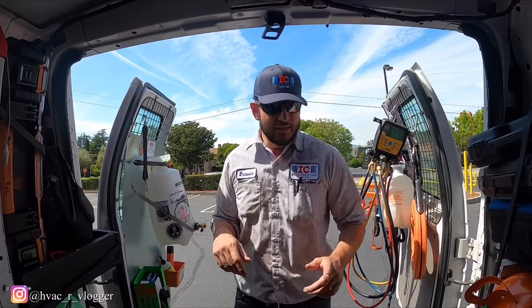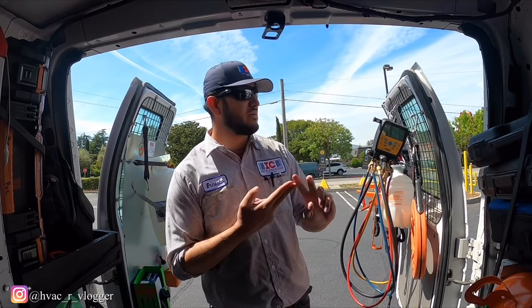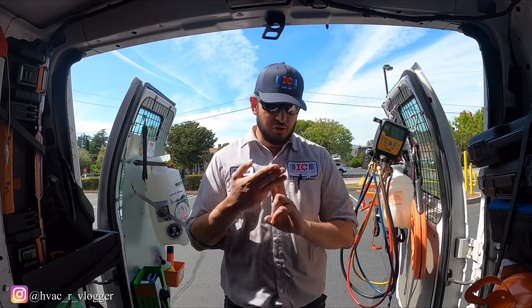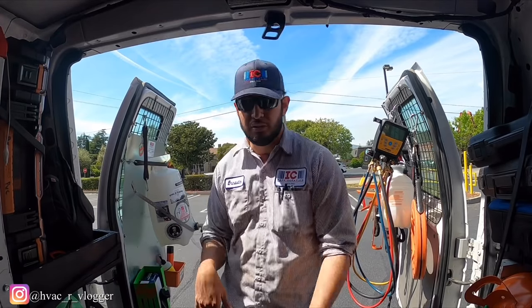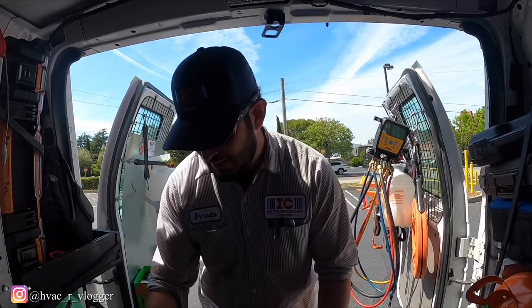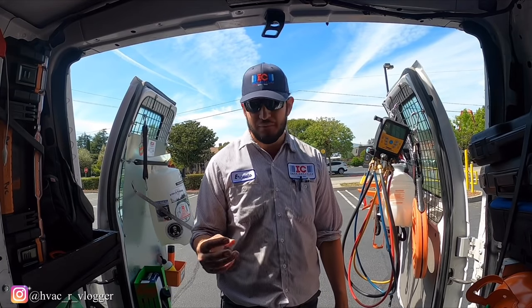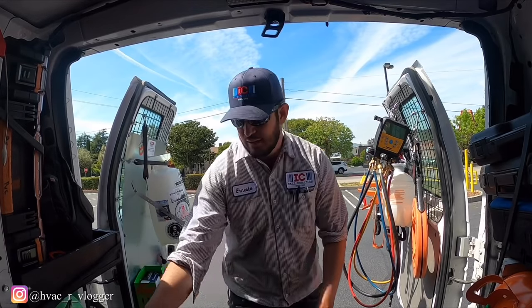In my experience, guys, that's one of the most common things with those ice machines: the bin control or a dirty coil. Those are the most common, a dirty coil or basically a dirty unit. And probably the third most common thing that goes out is the float switch on them, that they're super dirty or things like that.